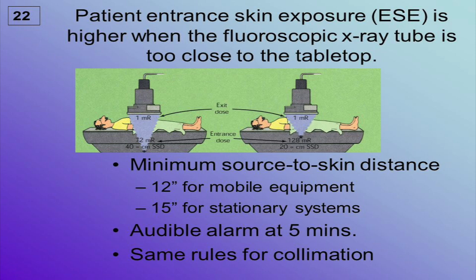Patient entrance skin exposure is higher when the fluoroscopic x-ray tube is too close to the tabletop. The minimum source to skin distance is 12 inches for mobile unit and 15 inches for stationary unit.